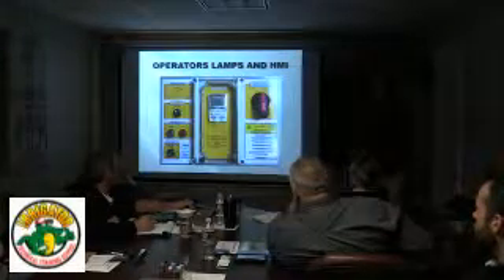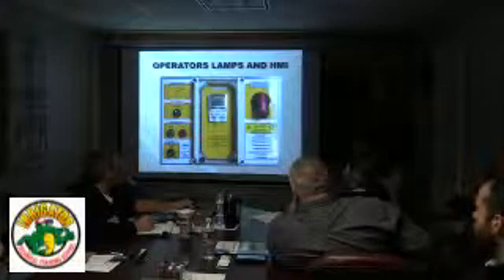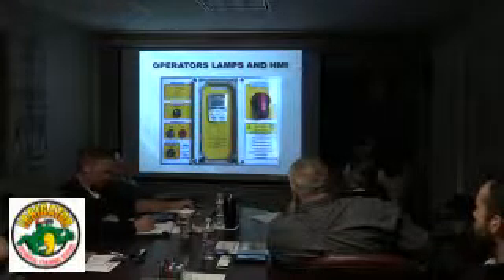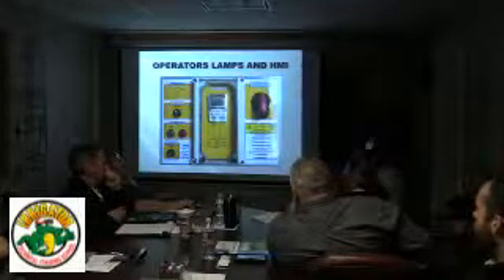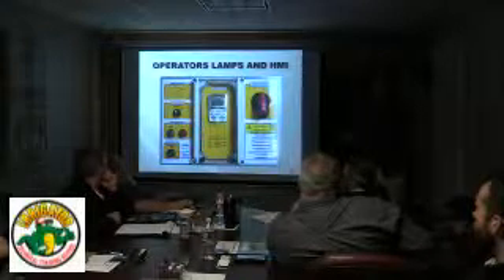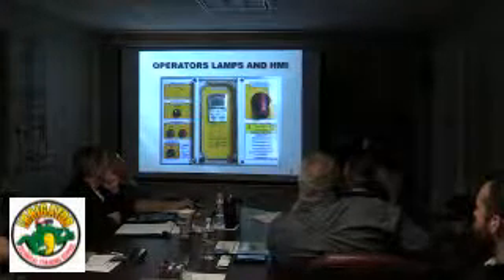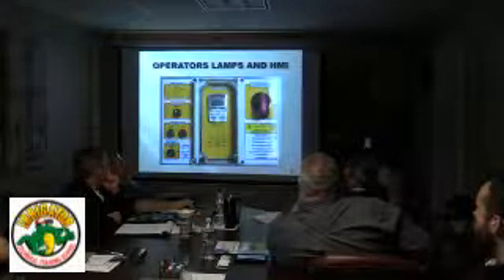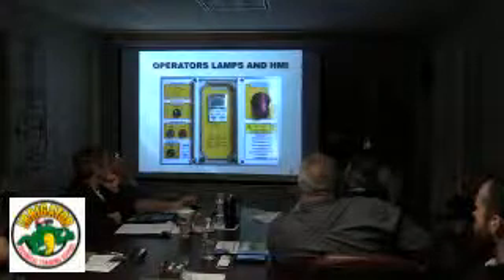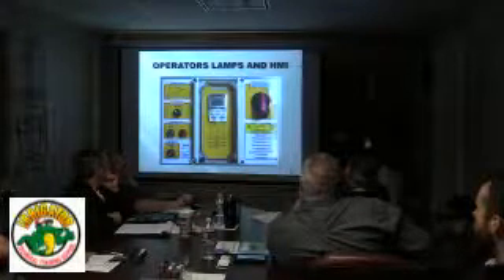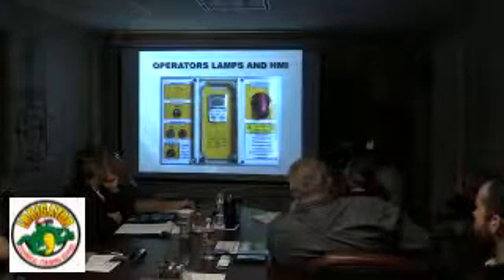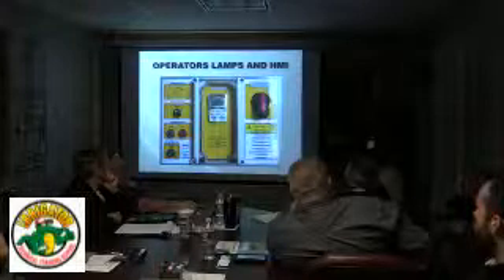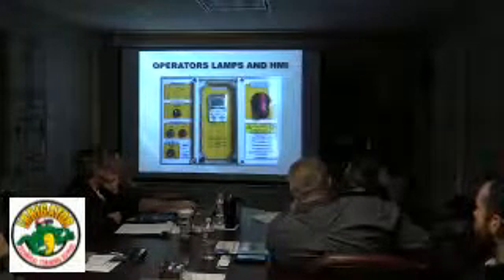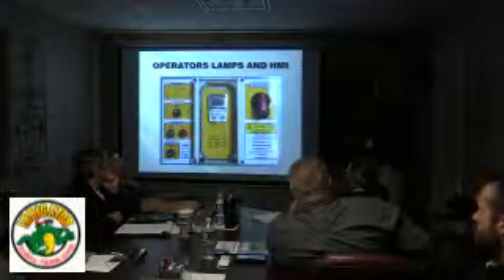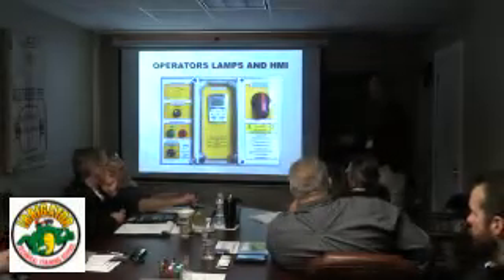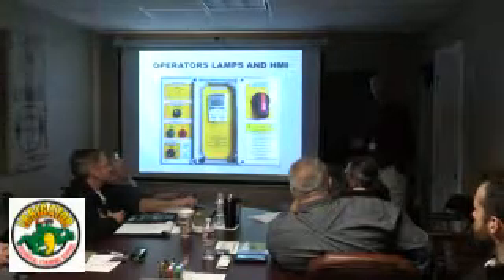I did want to mention one other thing back on this one. Notice up here it's got a local remote. This one's not being used, but we will put that in as a default, and if we do use it, we'll put a switch there. If you're in local mode, that's local to this panel. That means that it's going to run no matter what. It doesn't have to wait for a remote signal of any kind. If it's in remote, that means that even though it's in auto, it's going to wait for some kind of outside signal, like a sprinkler clock, a master valve with a sprinkler clock, a pivot, whatever you might have. It's going to wait for a signal from that outside source before it starts. Now, again, hand will override that. It'll start in hand regardless.